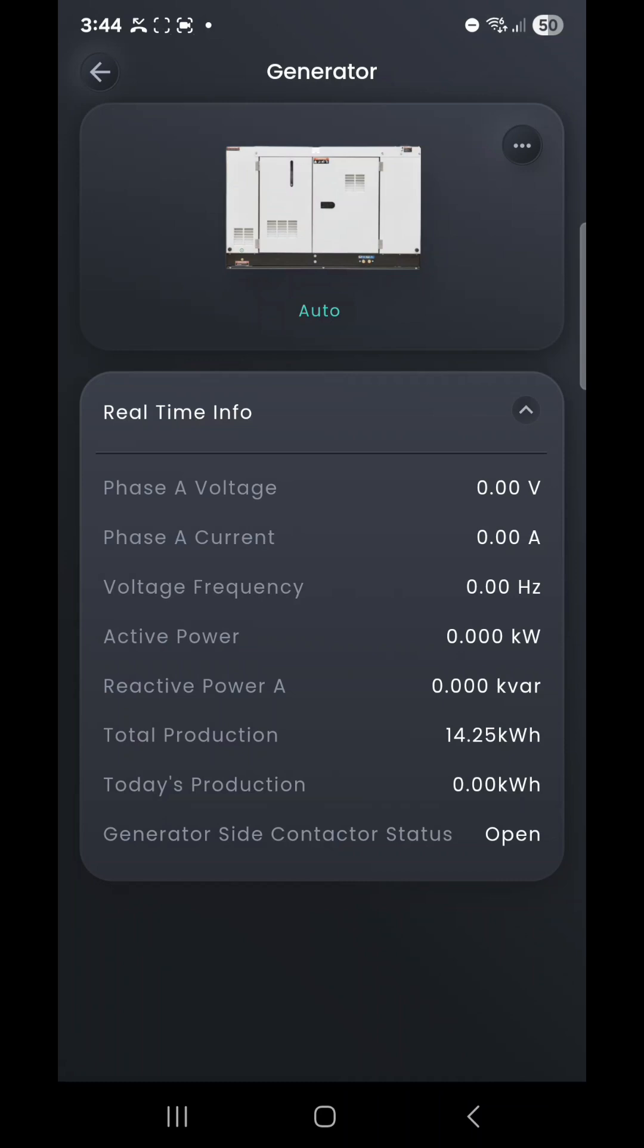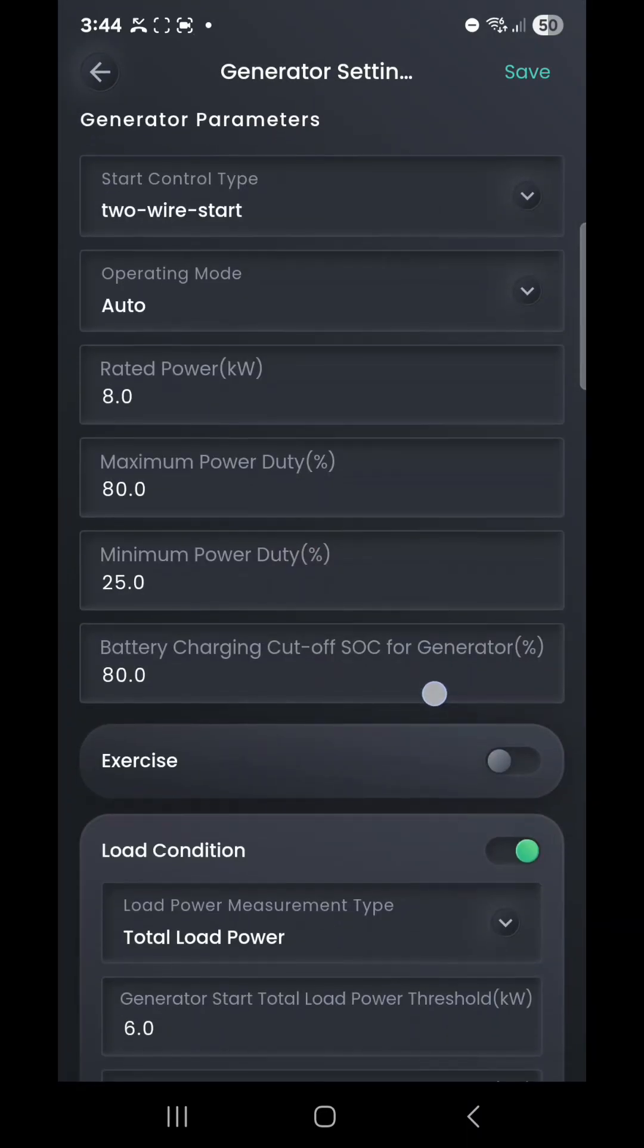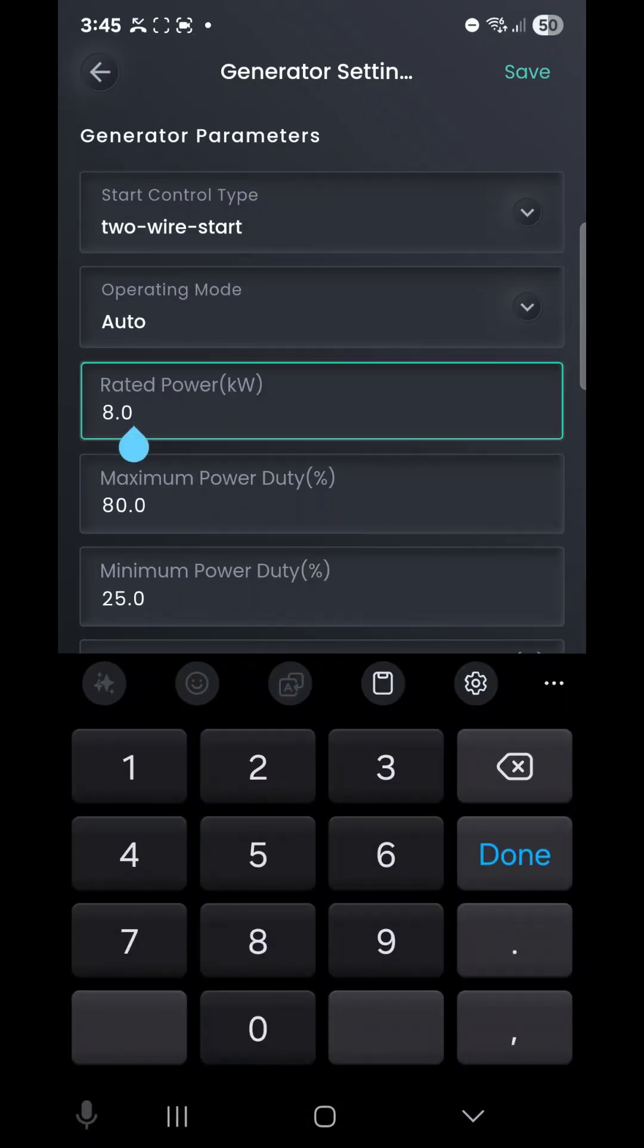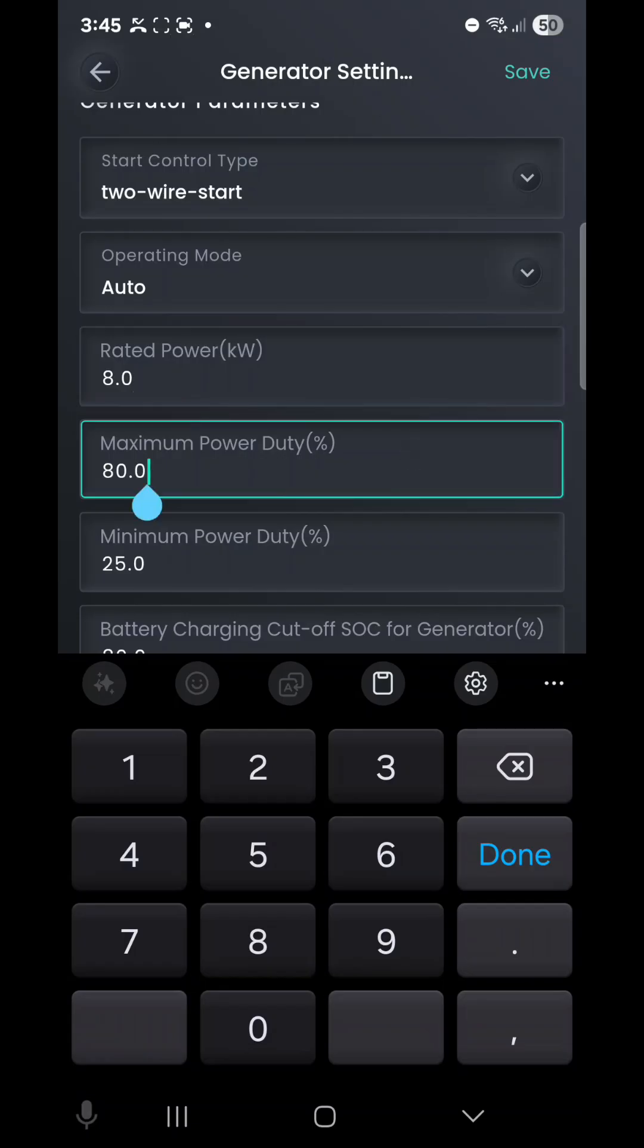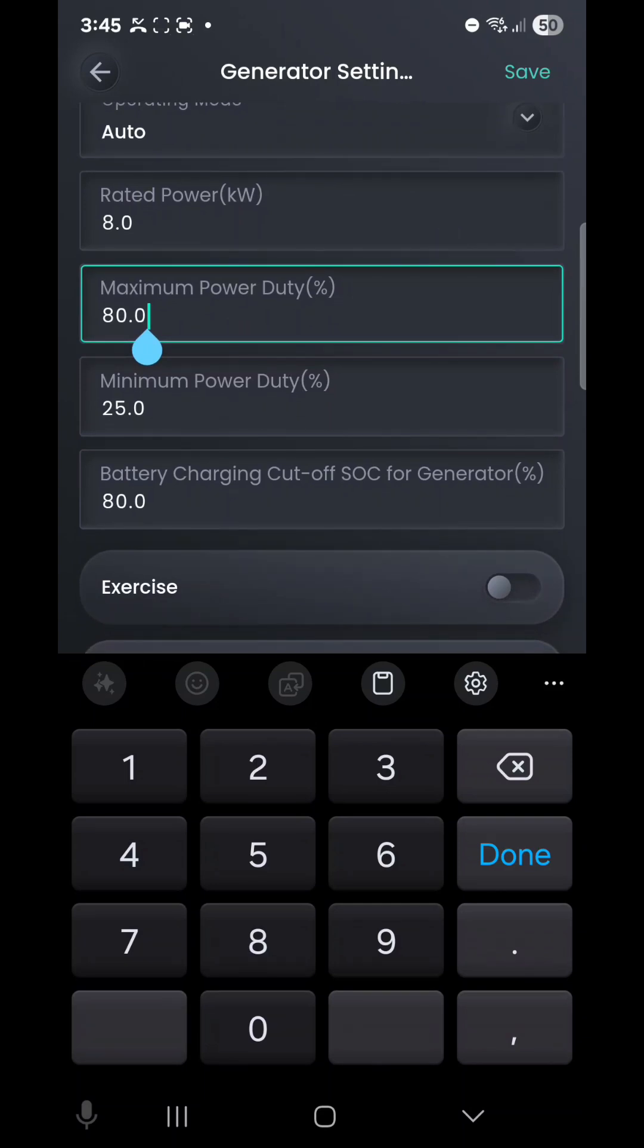If we wanted to change some parameters here, we can go into those three dots on the top right-hand side once more and wait for our menu to load. We can see here in generator parameters we've got our generator rating for the load. This will be based on the size of the generator and its output capabilities. I recommend not tampering with your maximum and minimum power duty cycle, as the installer will generally do this for you based on that particular generator.